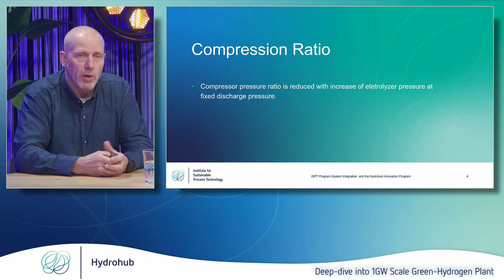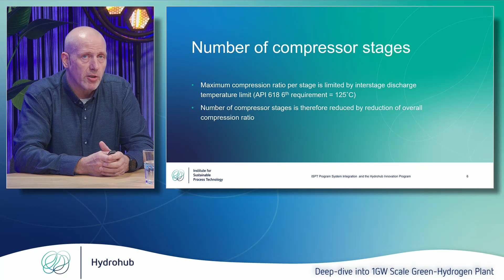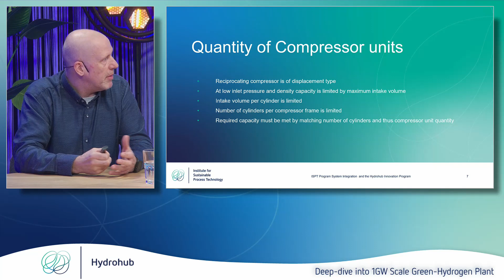And then the number of compression stages: the compression ratio per stage is limited by the discharge temperature. API 618, or the newer version, limits that at 125 degrees C. Therefore, the number of compression stages is reduced by the reduction of the overall compression ratio. So that leads to the quantity of compressor units. These are reciprocating compressors, so they are of a displacement type, with low inlet pressure and density. The capacity is limited by the maximum intake volume. The intake volume is limited per cylinder, and each compressor frame can only have so many cylinders mounted on it. So the required capacity is then met by simply increasing the number of compressor units.